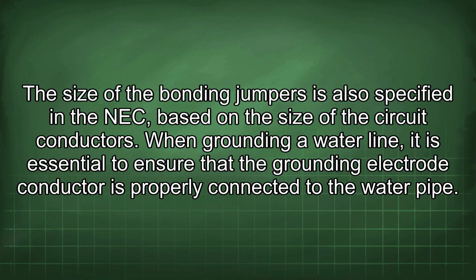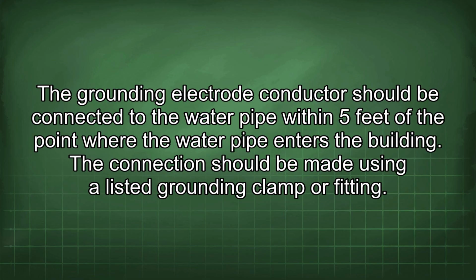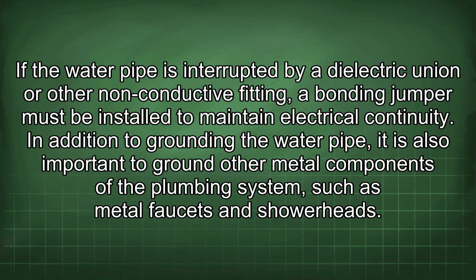When grounding a water line, it is essential to ensure that the grounding electrode conductor is properly connected to the water pipe. The grounding electrode conductor should be connected to the water pipe within 5 feet of the point where the water pipe enters the building. The connection should be made using a listed grounding clamp or fitting. If the water pipe is interrupted by a dielectric union or other non-conductive fitting, a bonding jumper must be installed to maintain electrical continuity. In addition to grounding the water pipe, it is also important to ground other metal components of the plumbing system, such as metal faucets and shower heads.